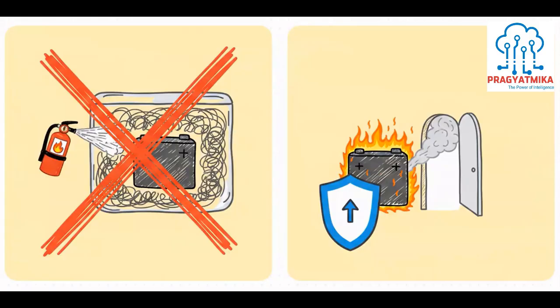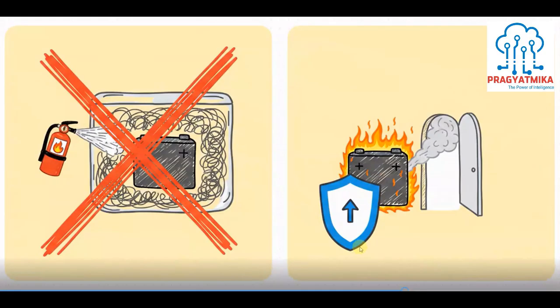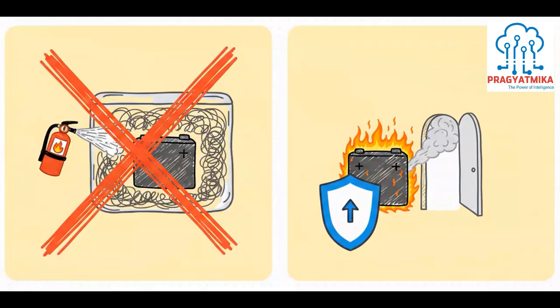Why? If you suppress a battery fire without fully cooling the core, the batteries continue to off-gas highly flammable vapors. If those trapped gases fill the enclosure and suddenly mix with oxygen—say when a first responder opens a door—it triggers a massive explosion.